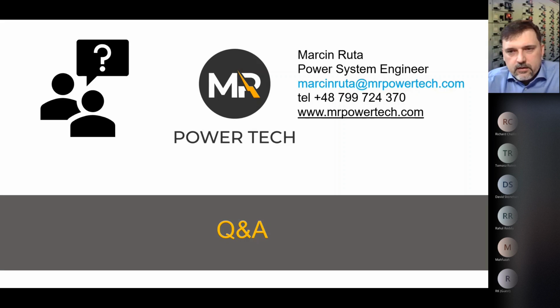And when you look at the remote operation, you have to keep in mind that it's not that we cannot go to the panel and do something. We can still do normal switching, and this is part of the likelihood of occurrence of arc flash, but also, NFPA says normal operation is allowed. It's not a big issue. Sometimes we might go through risk assessment and say, yeah, we still don't want to do it because we are a bit afraid of it, but that's a separate topic.